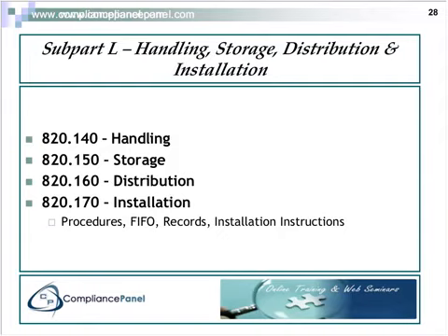There's also a requirement that you keep records of any installations you perform. If you're installing a big system such as an MRI system, you need to keep the records of those installations, and you also have to write instructions for how the installation should be done. In some cases, for very large equipment such as an MRI system, you would get a site plan from the hospital, or you would provide them with a site plan as to how much area they need to install a device such as that. That's where installation instructions would be important.